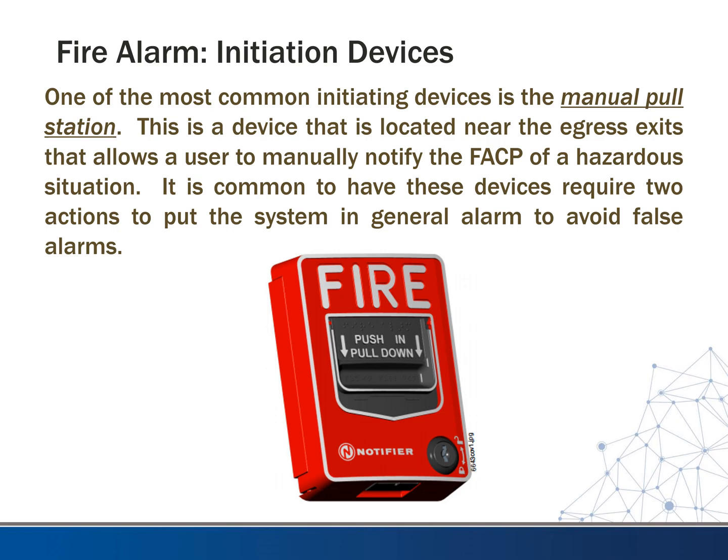Most fire alarms specified today require pull stations to have dual action. Sometimes there's a clear plastic cover over the device, so you have to lift the cover and then pull down. In schools especially, lifting the cover will set off a local alarm — it doesn't put the fire alarm control panel into supervisory or general alarm, just a small local alarm. You then have to pull down the lever to actually put it in general alarm. This avoids nuisance trips because when kids pull the cover up and hear the local alarm, it usually scares them enough that they put it back down.